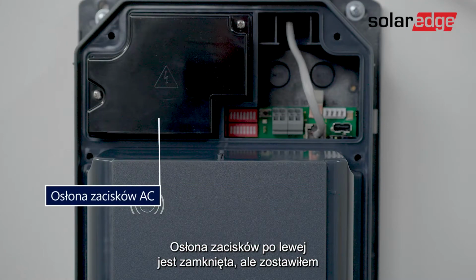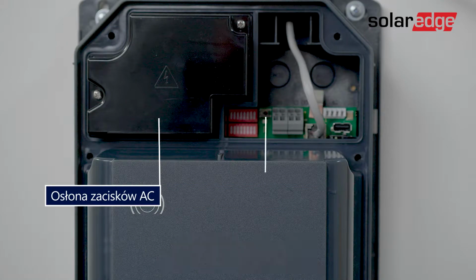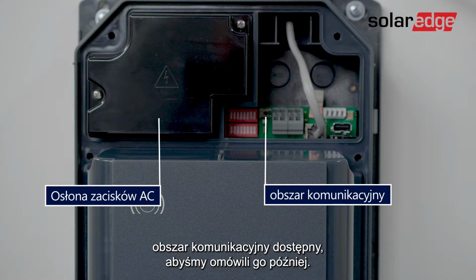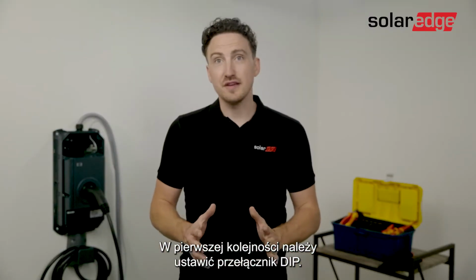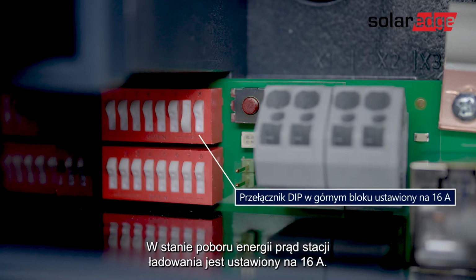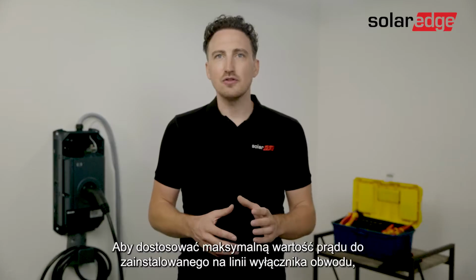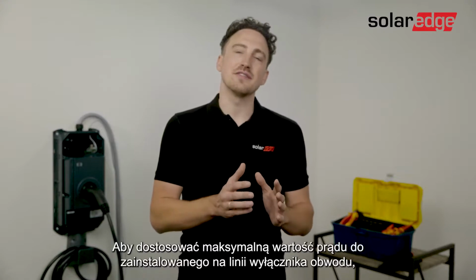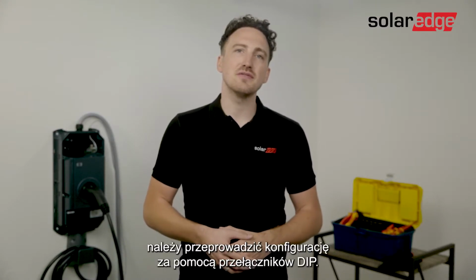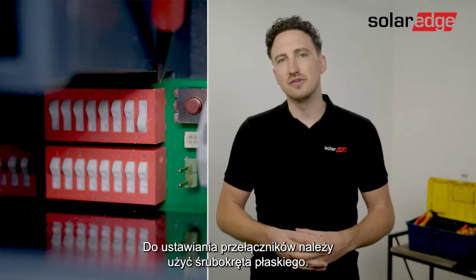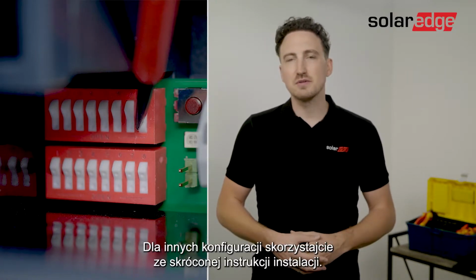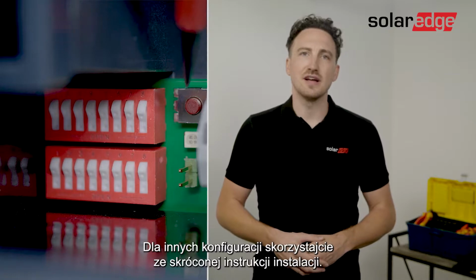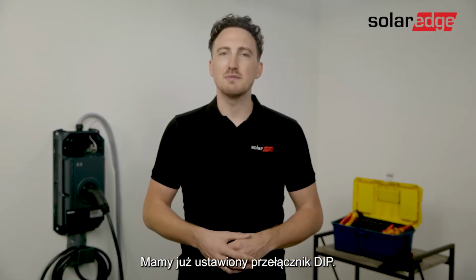Okay. The terminal cover on the left is closed, but I left the communication area accessible and we will cover it later. Now, first thing you want to do is set the dip switch. The charging station is set to 16 amps in the delivery state. In order to adapt the maximum current to the installed line circuit breaker, a configuration via the dip switches is necessary. To move the switches, you should use a flat screwdriver, and for alternative setups of current, use the quick installation guide. Alright, we have our dip switch set.